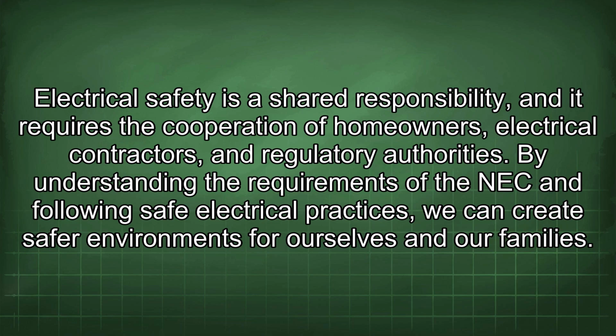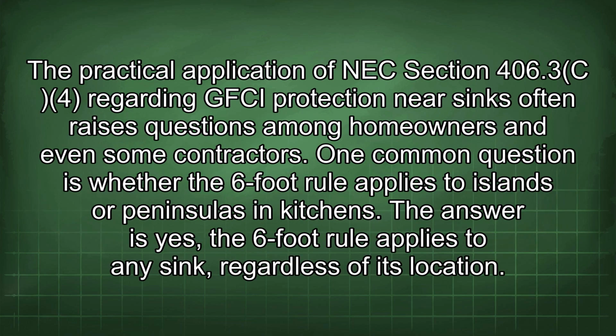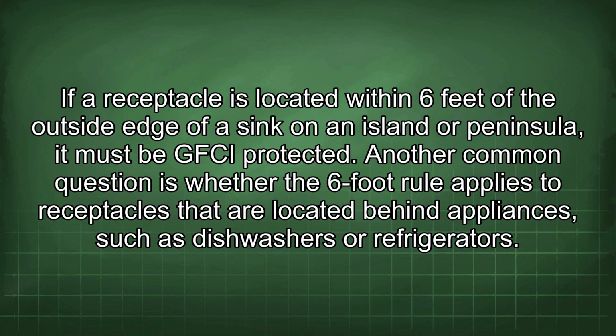our families. The practical application of NEC Section 406.3(C)(4) regarding GFCI protection near sinks often raises questions among homeowners and even some contractors. One common question is whether the 6-foot rule applies to islands or peninsulas in kitchens. The answer is yes, the 6-foot rule applies to any sink, regardless of its location. If a receptacle is located within 6 feet of the outside edge of a sink on an island or peninsula, it must be GFCI protected.